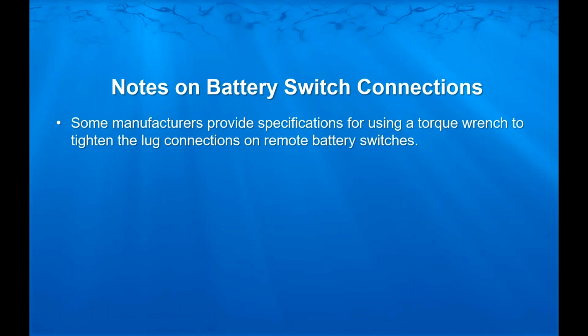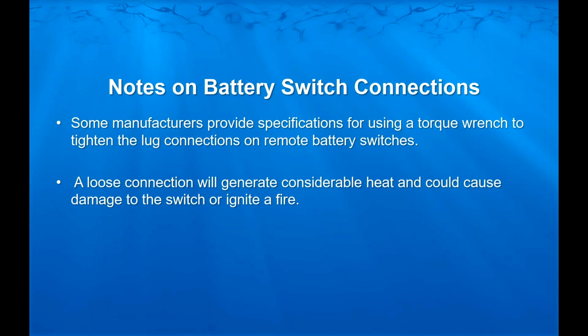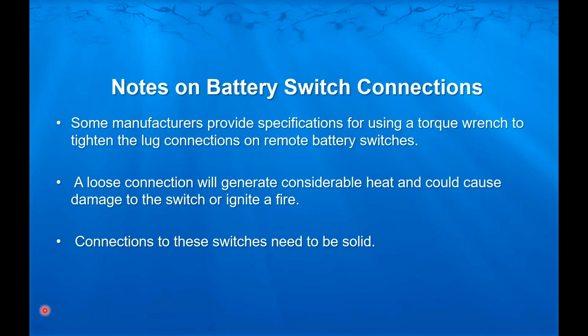And so some final notes on battery switch connections. There are some manufacturers that provide specs for using a torque wrench to tighten those lug connections. You've got to make sure that they are secure. A loose connection is going to generate considerable heat, and heat is the main result of resistance. It could damage the switch. I've seen switches where the switches got so hot that the studs molded into the plastic switch just popped out because it turned to gel. Connections to those switches need to be solid. We're talking about an area where there's a very high current flow, very big cable, and any loose connections there are going to have some pretty dire circumstances. So make sure that those battery switch connections are very secure.